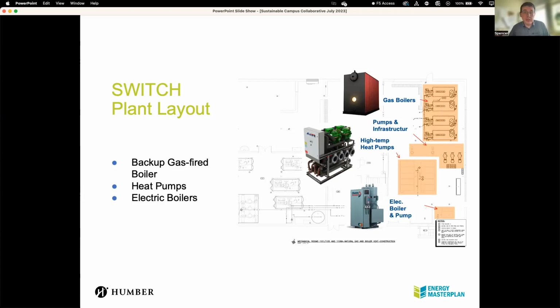One, we're still going to need some gas heat on the coldest days. Two, for redundancy - if the power goes out, we want to be able to heat the building, because we can't have an emergency generator big enough to do it electrically. Third, we think the Ontario electrical peak is going to switch to the winter, in which case we'll need this for load shedding. So there's gas boilers - they're already in, they've just arrived, they're getting hooked up.